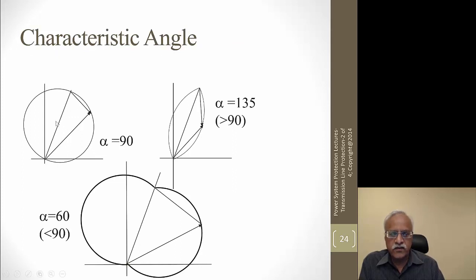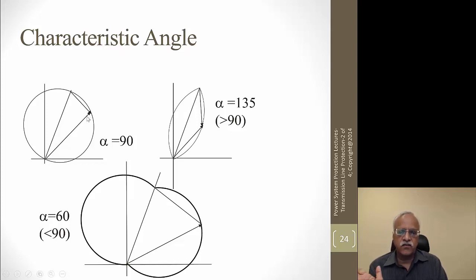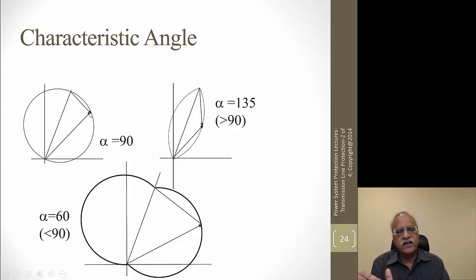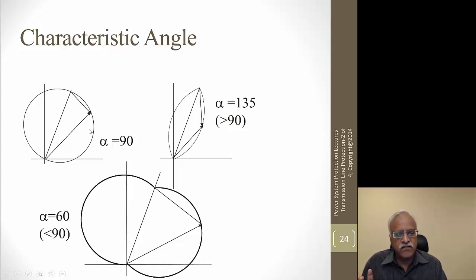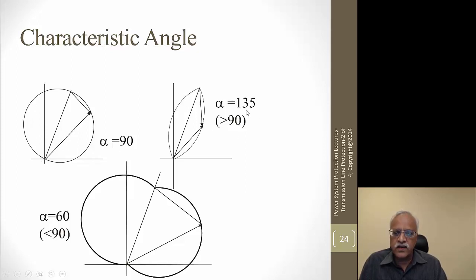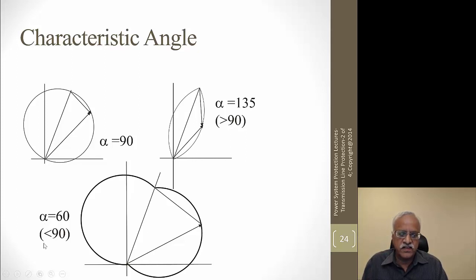If the characteristic angle is changed to 135 degrees, the characteristic becomes a lens or elliptical shape. If the angle is less than 90 degrees — say 60 degrees — it becomes a tomato-shaped characteristic. This is how distance relays are designed. The key takeaway is that the secondary impedance you set on the relay is based on the CT ratio, and the relay measured impedance equals the primary impedance multiplied by CTR divided by PTR.